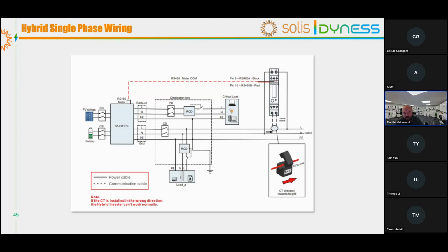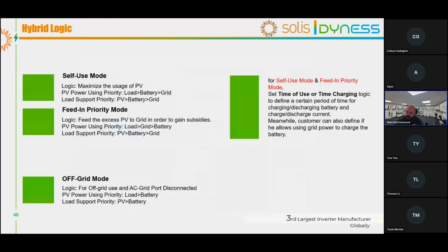The other point to note about CTs is that if you have it connected on the wire but don't have it clicked properly, so if you look at the bottom right hand of that slide, if you don't have it completely closed properly, then you'll not get accurate information to the meter. And if you don't get information to the meter, then the inverter doesn't understand what's going on. So that's the general installation for it.